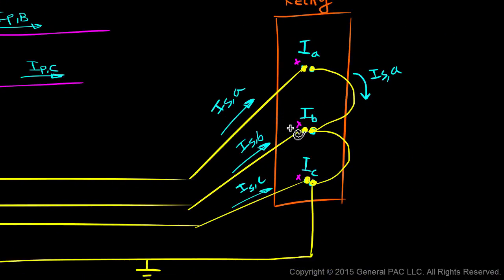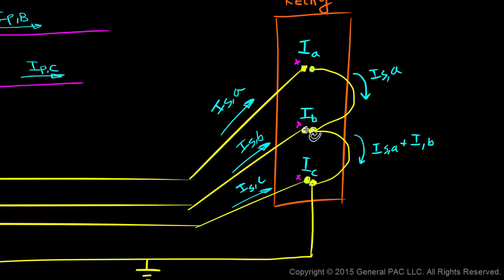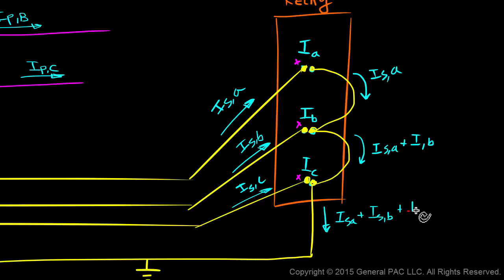Let's zoom in to get a better look. What goes into the polarity-mark input terminal for phase B is essentially the secondary phase B current. But what comes out of the non-polarity side is essentially phase A current plus phase B current. Phase B current flows into the polarity side of the input terminal, and phase A current flows into the non-polarity side. What comes out is the sum of what goes in: phase A plus phase B current. Similarly for phase C, what comes out is the secondary phase A current plus secondary phase B current plus secondary phase C current — the sum of what goes in.